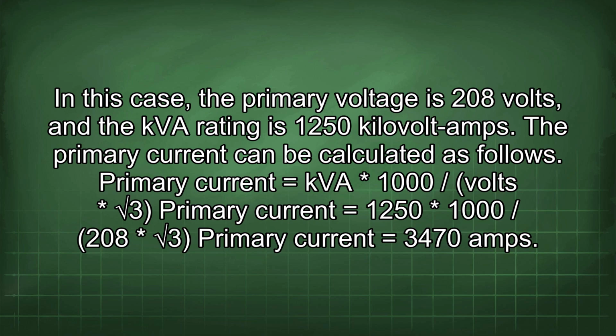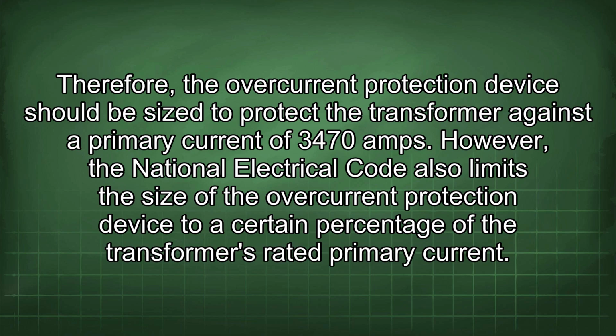The primary current can be calculated as follows. Primary current equals kVA * 1000 / (volts * square root 3). Primary current equals 1250 * 1000 / (208 * square root 3). Primary current equals 3470 amps. Therefore, the overcurrent protection device should be sized to protect the transformer against a primary current of 3470 amps. However, the National Electrical Code also limits the size of the overcurrent protection device to a certain percentage of the transformer's rated primary current.